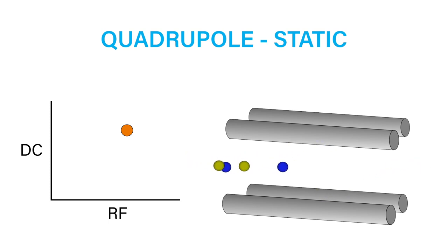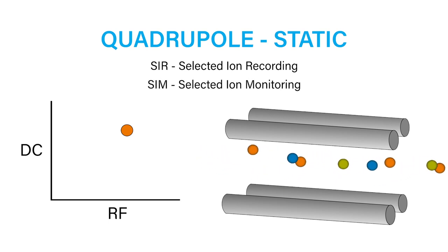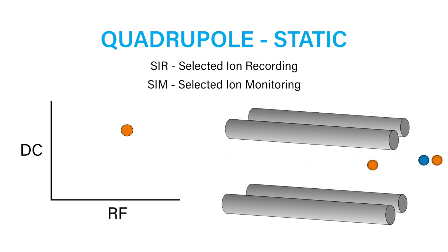This is the most common mode used in quantitative analysis since it is the most sensitive and additional information is not needed. On a single quad, this is called SIR or Selected Ion Recording. This mode may also be called SIM or Selected Ion Monitoring.